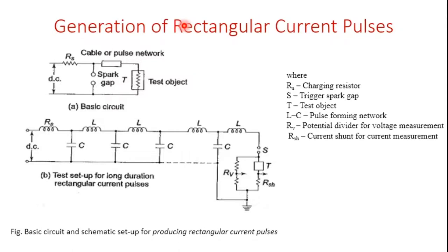Next, we have the generation of rectangular current pulses. Rectangular current pulses of high magnitude can be generated by discharging a pulse network or a cable which was previously charged. The basic circuit for generating rectangular current pulses uses a cable or equivalent pulse network charged to a specified value with the help of a DC supply.